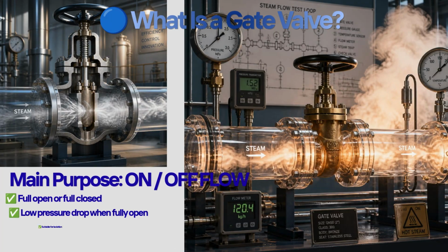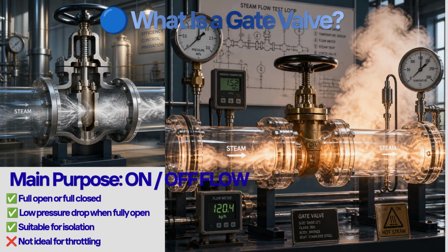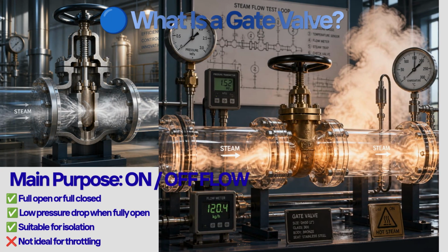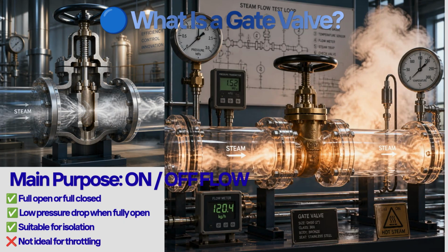A gate valve is primarily used for isolating a pipeline. When fully open, the gate moves out of the flow path, allowing fluids to pass with relatively low pressure drop. Gate valves are generally intended for fully open or fully closed service rather than continuous throttling.